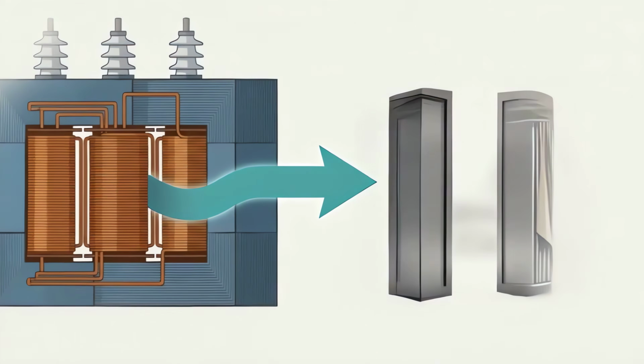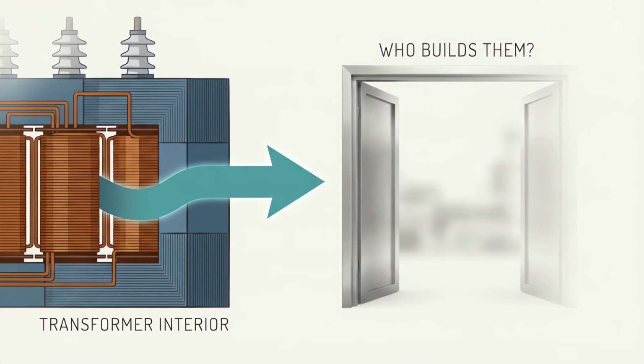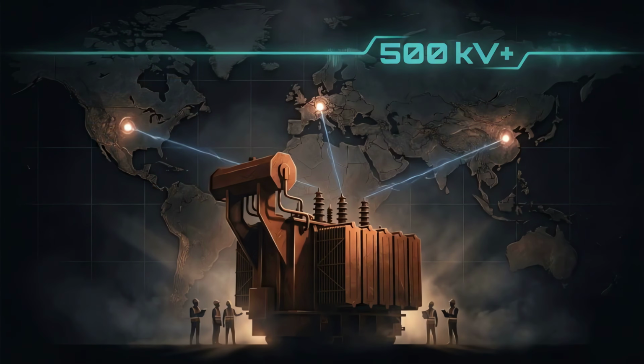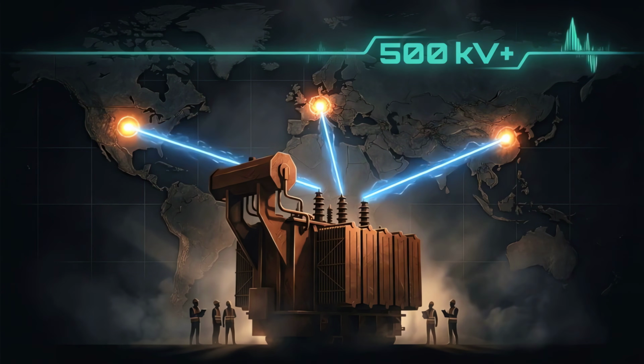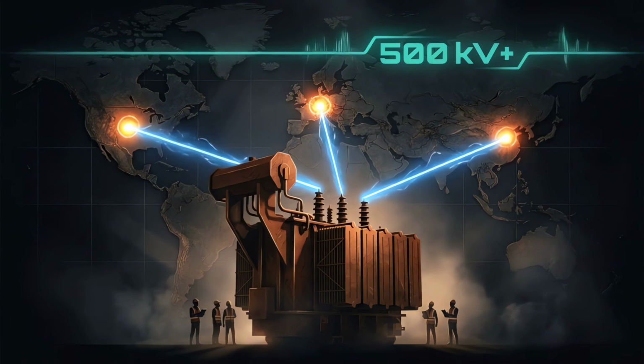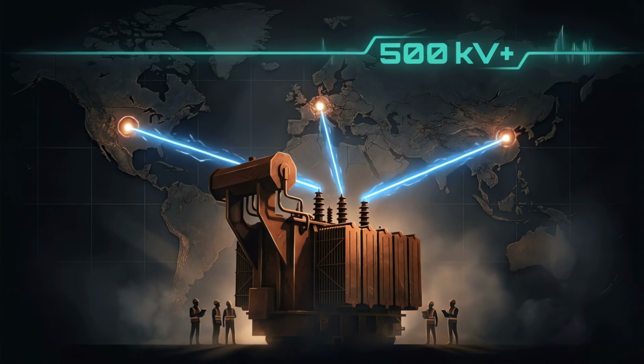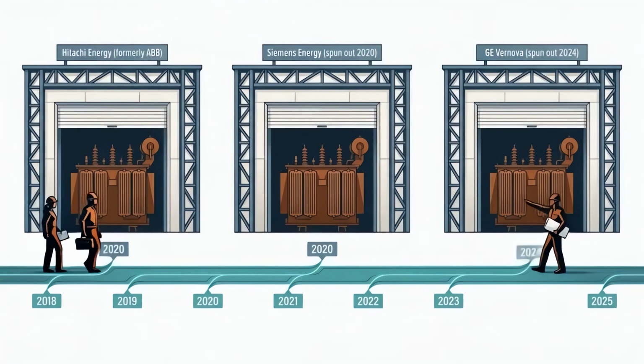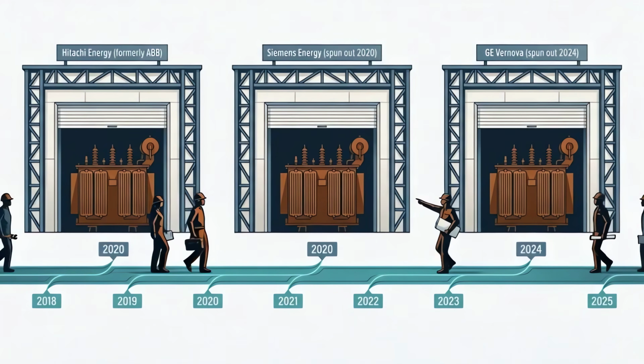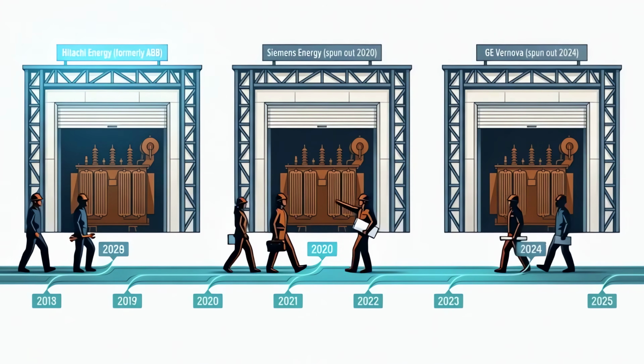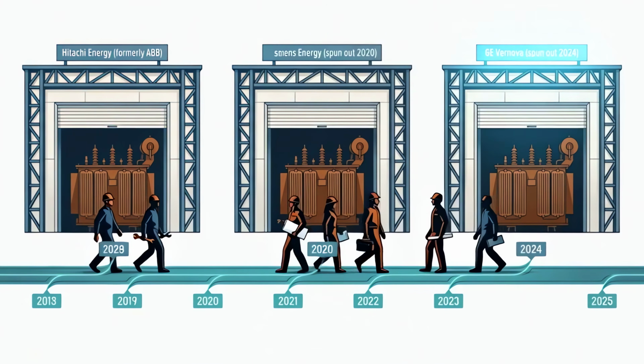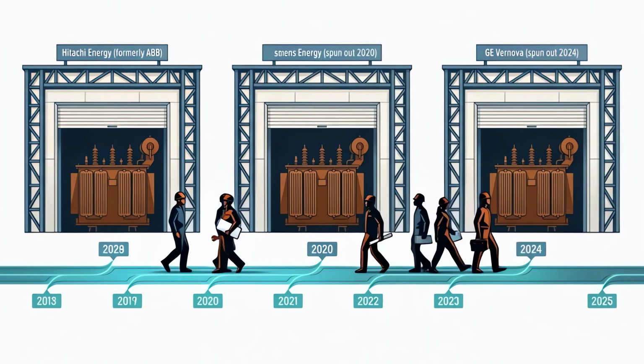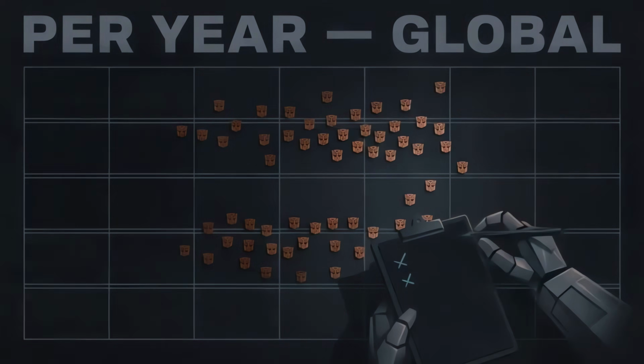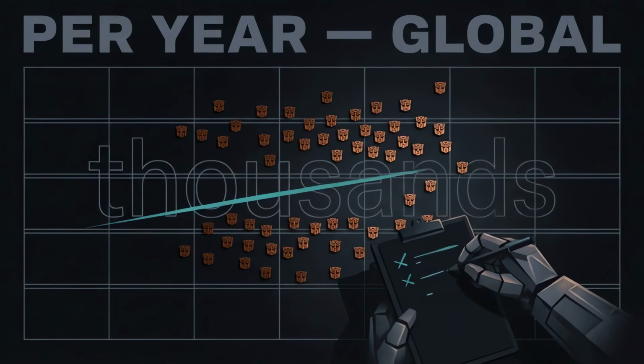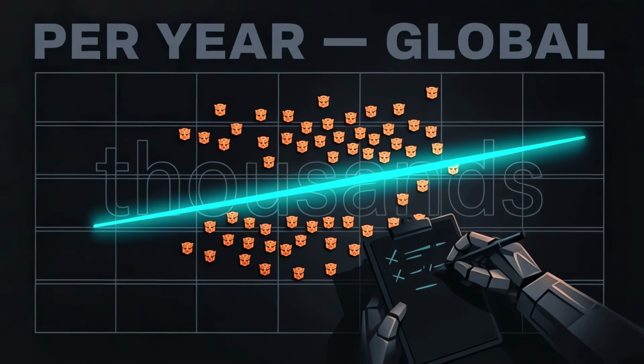Who makes them? If we're talking about the class an AI hyperscaler needs, 500 kilovolt and up, there are essentially 3 companies on Earth that make them in quantity: Hitachi Energy, which used to be ABB; Siemens Energy, which got spun out of Siemens in 2020; and GE Vernova, which got spun out of GE in 2024. Between them, they build in the low hundreds of these per year, globally. Not thousands, low hundreds. Lead times in 2019 were around 18 months.